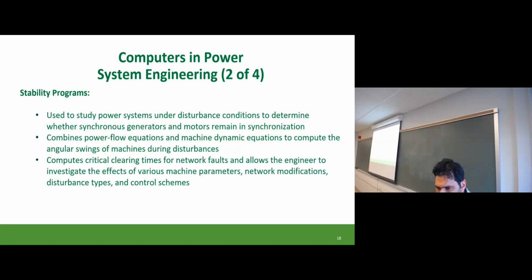The other type of program is stability. Stability deals with investigating how the power system would act in case a disturbance happens. A disturbance may not be a fault—sometimes turning on a generator makes it absorb a lot of power at starting, which looks like a fault from the grid side but isn't. After a few seconds or minutes, normal conditions are restored. So stability programs try to ensure our system gets back to normal operation after such an incident.